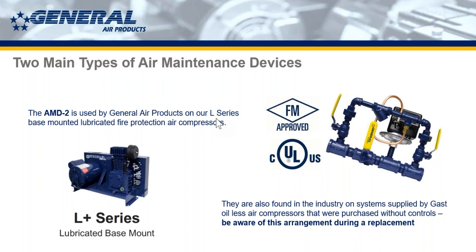So at General Air Products, we use our AMD2 in conjunction with our L series or L plus series base mounted lubricated air compressor. The base mounted lubricated air compressors are an old school style of air compressor that you don't have a pressure switch on typically. So, a pressure switch on a compressor is the brains of the compressor. It tells the compressor to turn off and on when certain pressures are reached.